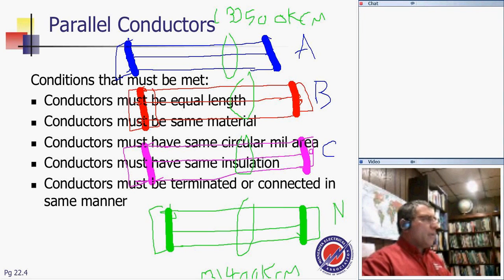Why would we parallel, guys? We parallel because we can't carry the current with a single conductor. The conductor is so big, so clumsy, that I can't carry it. Here's the rule of thumb for a lot of people for paralleling. If you can't carry the load with 500 kcm, or the equivalent, which is 380 amps, more than 380 amps, or you need a conductor more than 500 kcm, you parallel. So suppose I have a 600 kcm. It's a good idea to parallel.